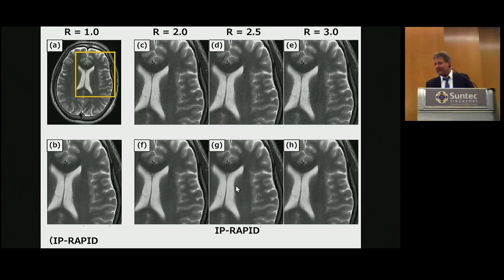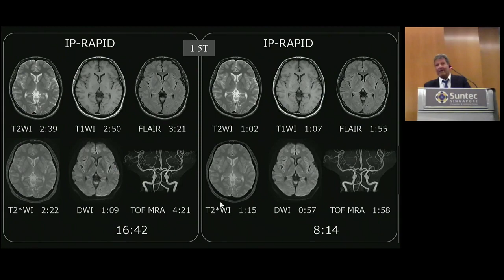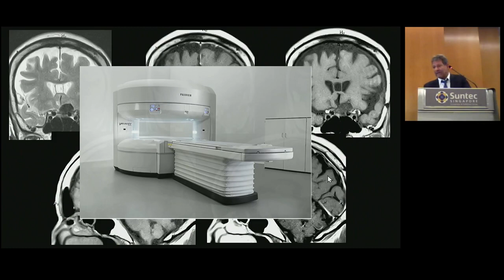Here you see a couple of examples from 1.5 Tesla scanners. Here's a typical suite of MR applications that took a respectable 16 minutes and 42 seconds using IP Rapid to reduce the scan time and maintain the signal. The Fuji 1.5T scanner was able to bring this down to only 8 minutes. And that's pretty respectable for 2024. And this is even before they get to the deep learning level of reconstruction. Now, I have the greatest experience myself using IP Rapid on our open systems. And there's some experience of ours.